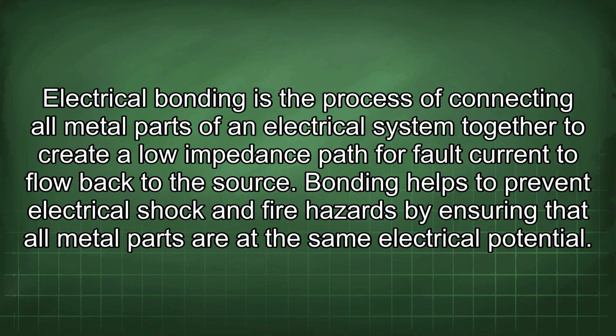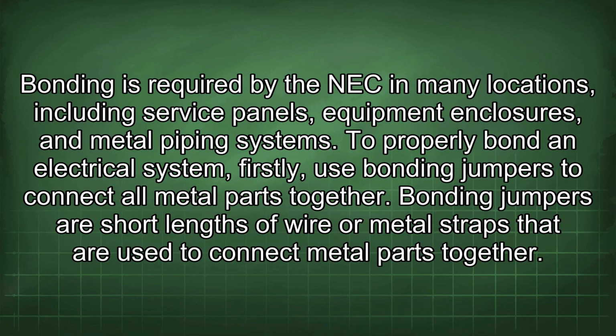Electrical bonding is the process of connecting all metal parts of an electrical system together to create a low impedance path for fault current to flow back to the source. Bonding helps to prevent electrical shock and fire hazards by ensuring that all metal parts are at the same electrical potential. Bonding is required by the NEC in many locations, including service panels, equipment enclosures, and metal piping systems.